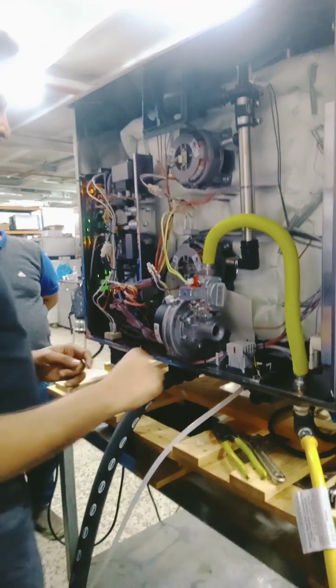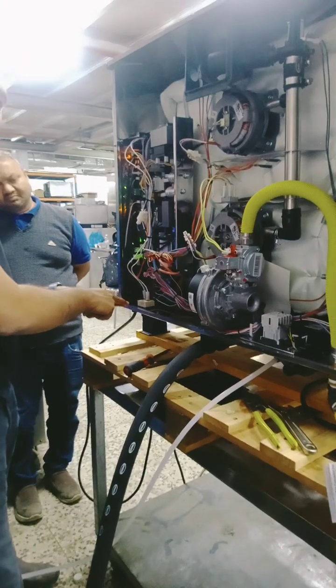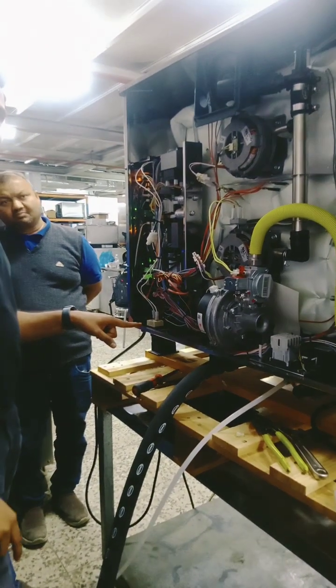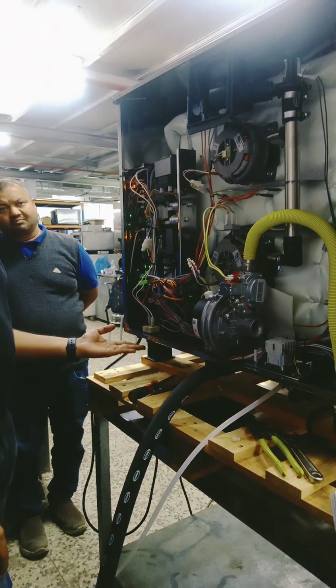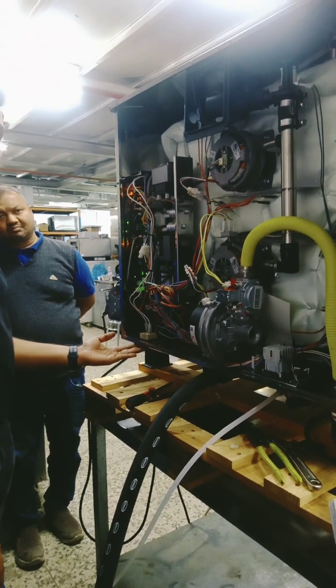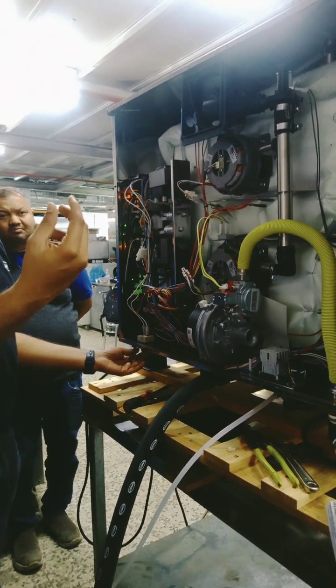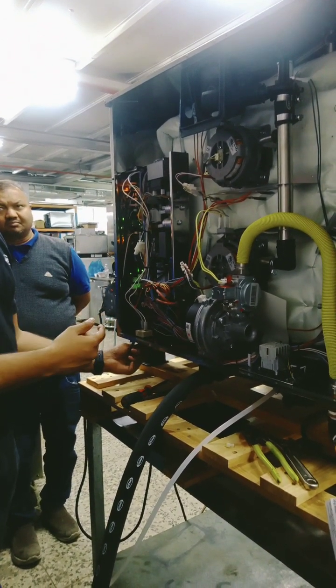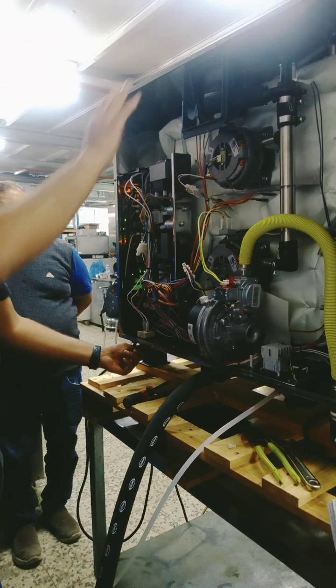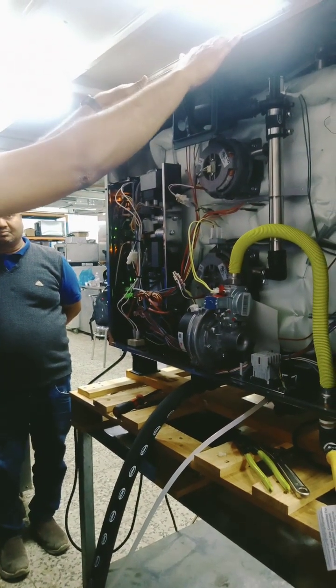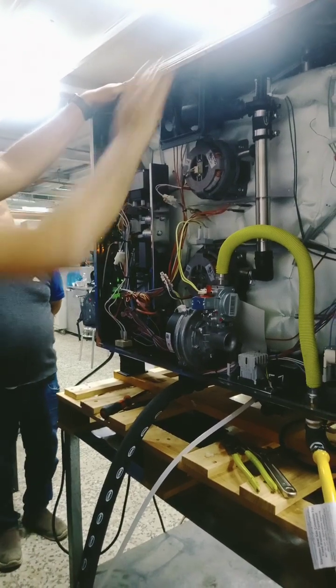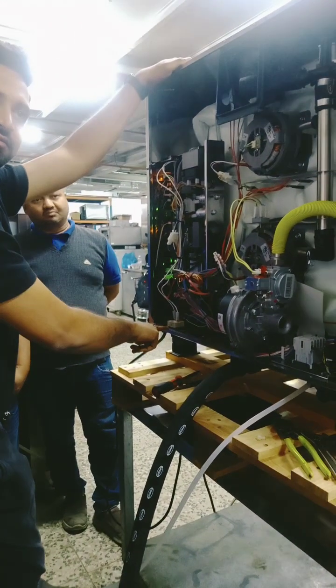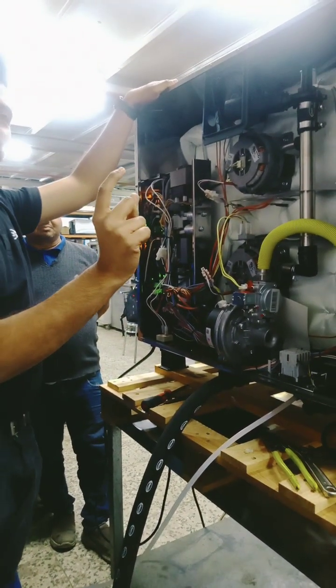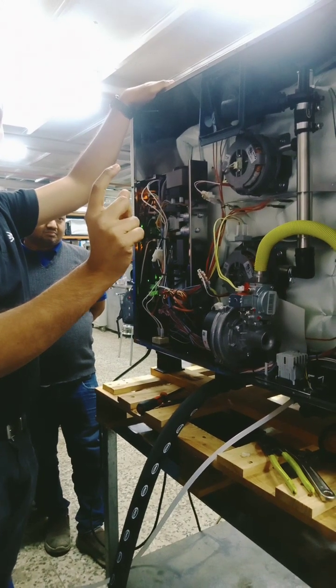Rewinding. Okay. And this is the safety thermostat. Everyone knows. How does this safety trip? How can it trip? When it reaches a higher temperature. The maximum oven temperature is 260 degrees, right? But this safety is 313 degrees. So we have a difference of almost 55 degrees Celsius.